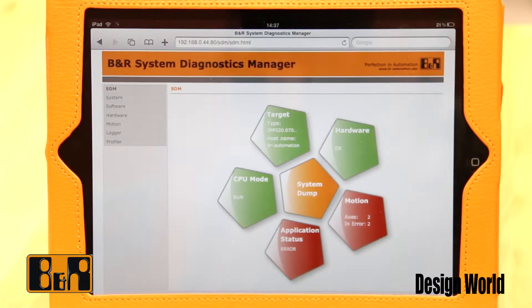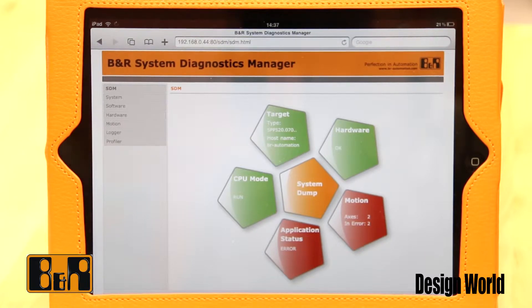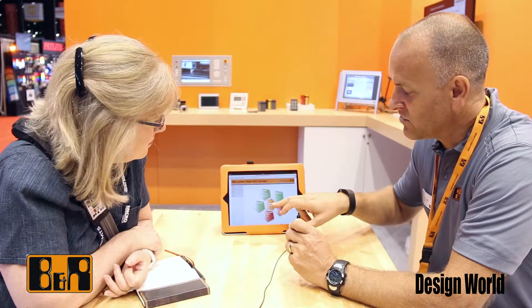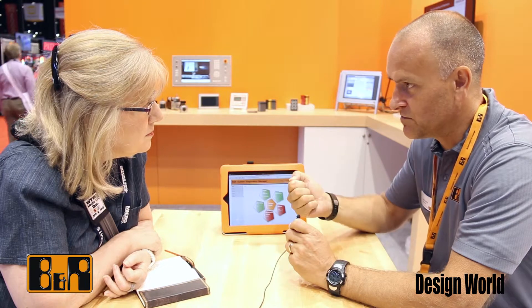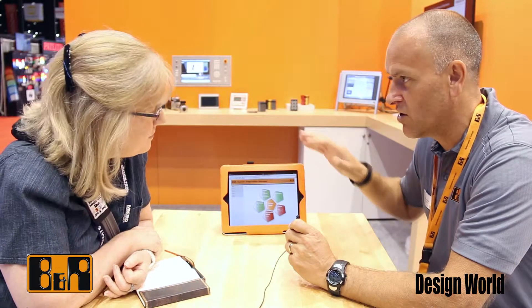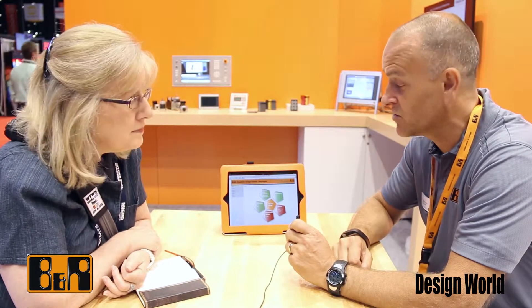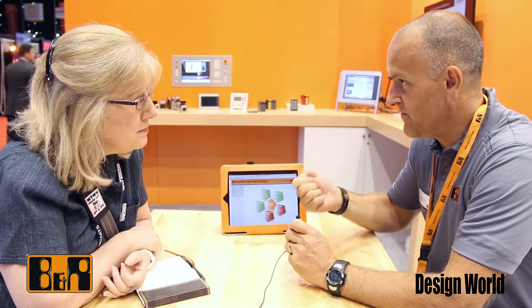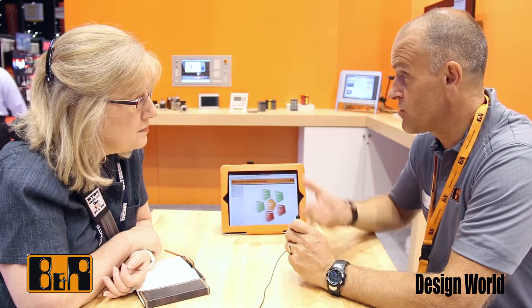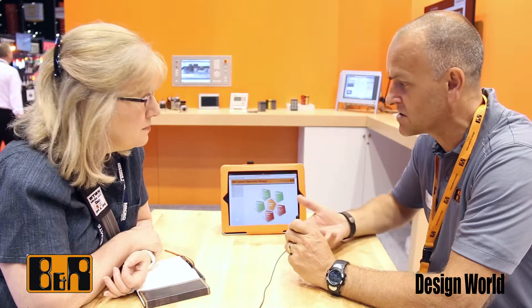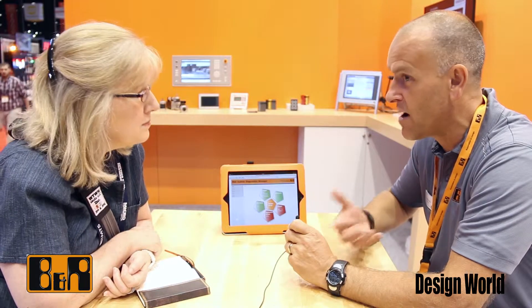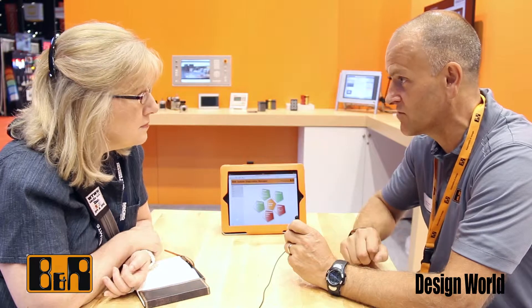It's a generic screen, but it shows you information on what is going on on the controller at any one time. This startup screen — the first screen you see — has a function called System Dump. When you press the System Dump button, it allows you to dump to a USB stick, onto the hard drive, or onto whatever you're connected to. That zip file can then be sent to someone who has the programming software — they can unzip it, and it contains traces, log books, and information on the hardware and how the whole system is running.